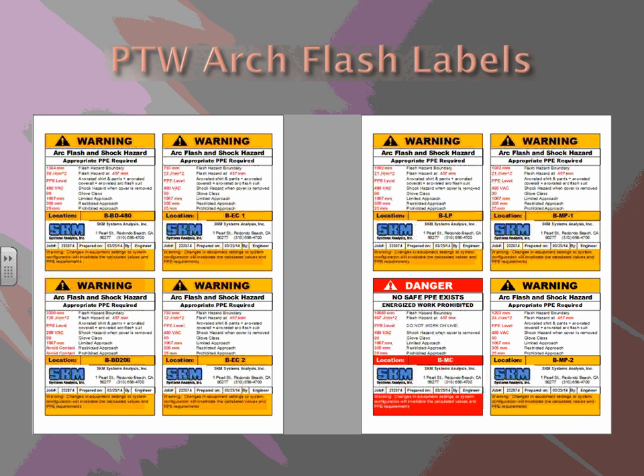Arc flash labels, basically going through, explains what can be worked on properly. This would be our feed coming from the utility. We don't have overcurrent protection coming straight from the utility, so that has to be turned off in order to work on it safely. But lighting panel, mechanical 1 panel, mechanical 2 panel, environmental chamber 2, 480 bus, and environmental chamber 1, showing all the PPE levels.